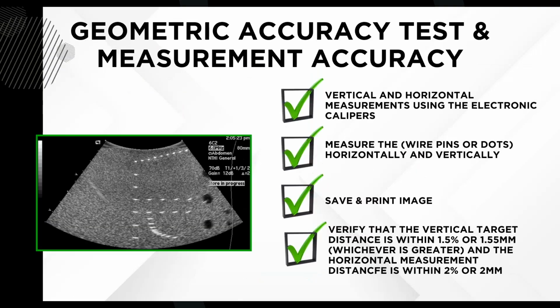Next test is a geometric accuracy test and measurement accuracy. For this particular test, we're going to hit vertical and horizontal measurements using the electronic calipers that we've been using. We're going to measure the wire pins or dots horizontally and vertically. We're going to save and print this image. Verify that the vertical target distance is within 1.5 or 1.55 millimeters, whichever is greater, and the horizontal measurement distance is within 2% or 2 millimeters.